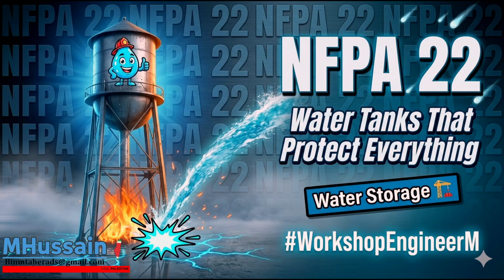But there's a critical, almost ironic thermodynamic twist that safety engineers must design into that vertical thermos. What's that? Section 15.2.2.2 requires that these frost-proof casings must have fire stops placed inside the casing at roughly 6 feet and 10 feet above the base. These fire stops are horizontal layers of tightly packed, non-combustible insulating material that block the vertical air cavity.